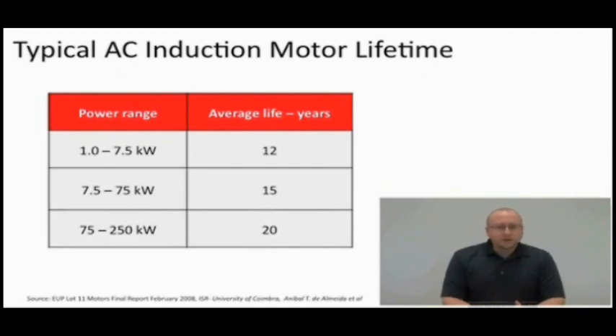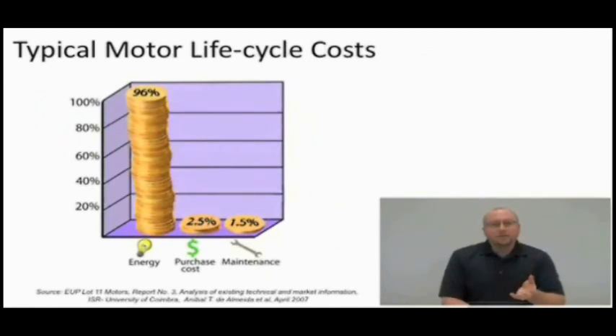You're going to save so much energy, because 96% of the cost of an AC induction motor is used for energy, just to run the motor. You can imagine how much it would cost to run a 10 horsepower motor 24 hours a day, 365 days a year, and we'll actually go through a couple of those calculations later. But even though it's relatively a smaller portion of the gains that you can make, it's still worth doing, because most of the energy cost is in running the system.